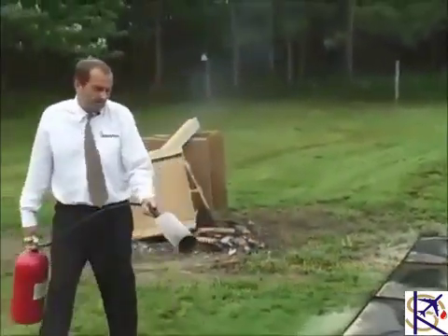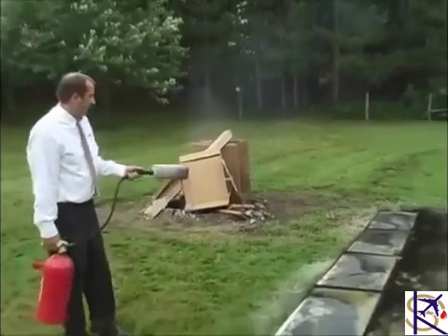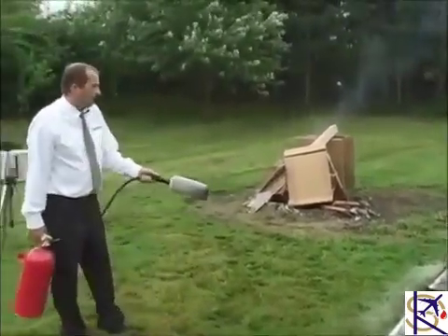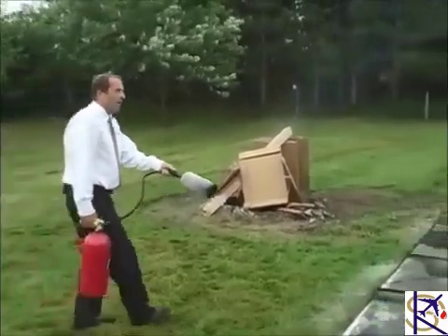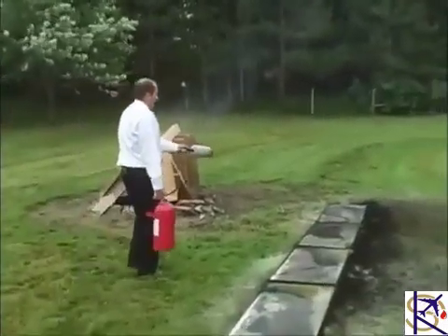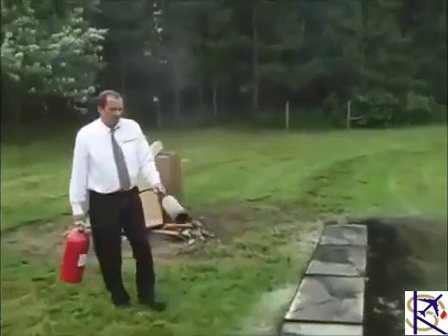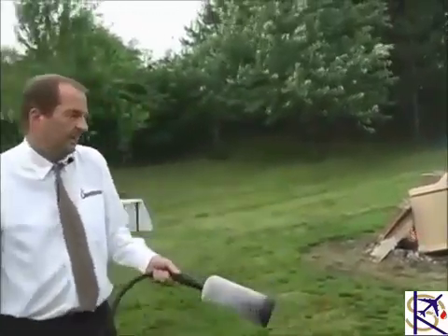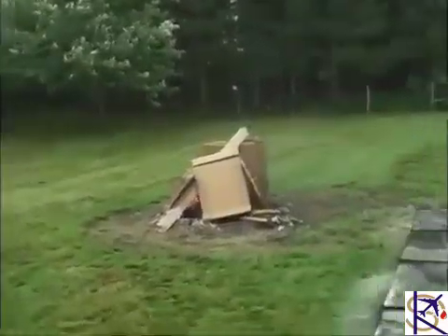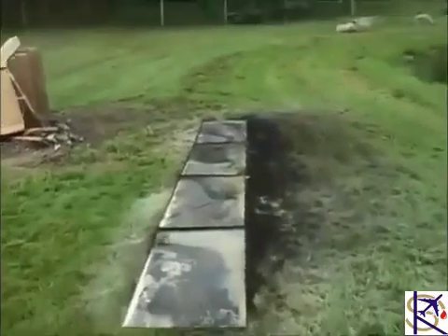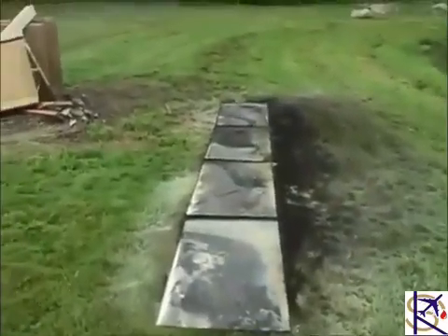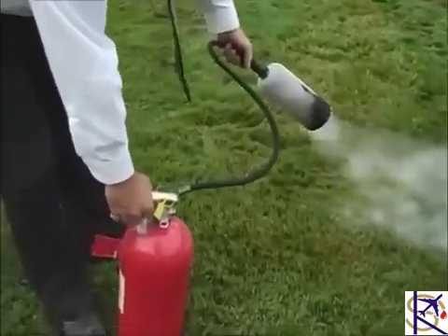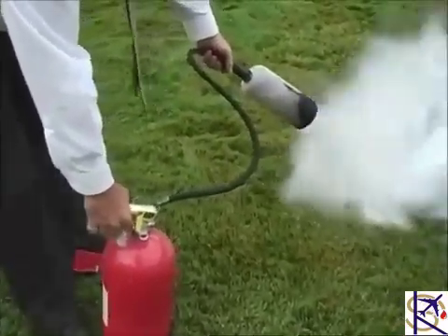Not as effective as an ABC, but still good for B and C fires. No residue left, very clean. Everything just evaporates. Carbon dioxide, what we're exhaling, is what came out of the extinguisher. Very cold, so be cautious of the nozzle. It's frozen, and sometimes if it's too heavy, you can leave it on the ground. Also a very large, very loud noise when the gas is discharging.